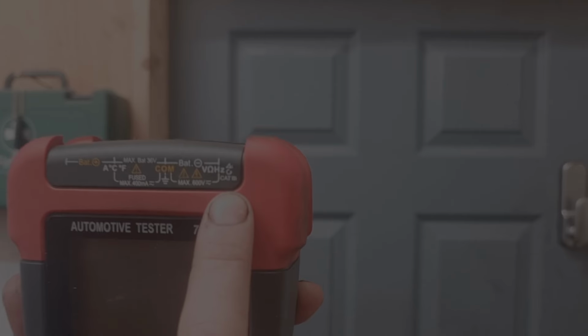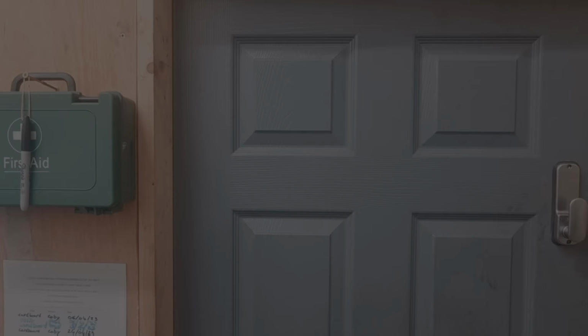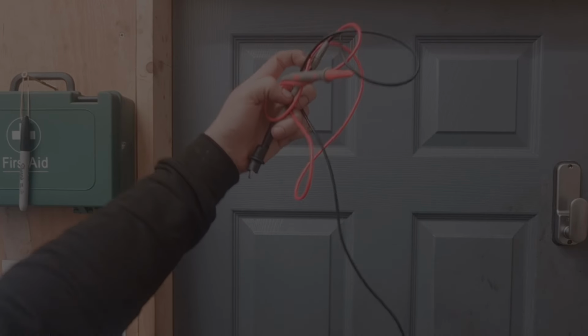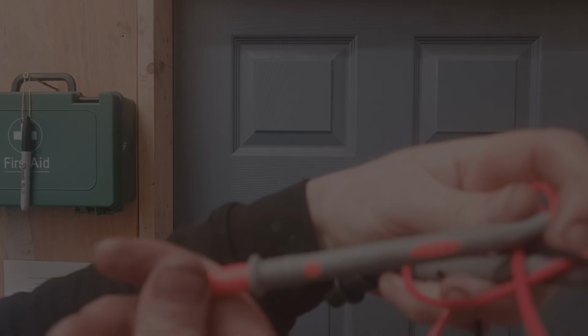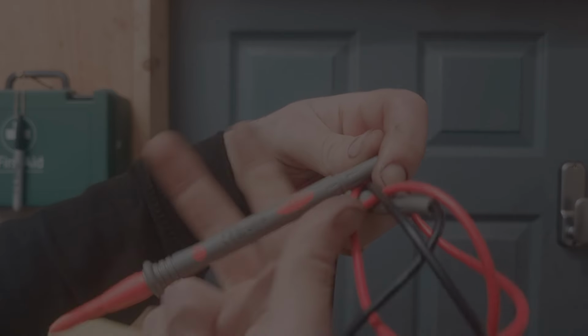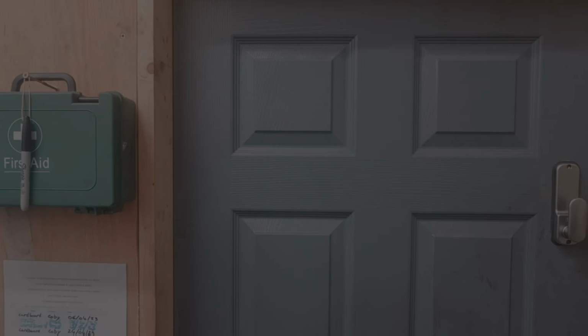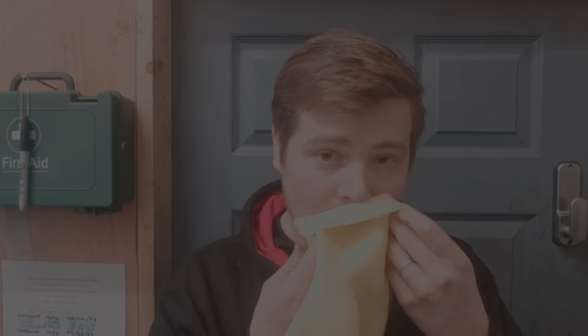Some of the tools we're using include a multimeter, and the multimeters have to be category 3, and so do the leads. You have to be careful with these because a lot of leads aren't actually rated. You'll see they're cat 3 because they have cat, if the camera will focus, they say cat 3 on them. The other thing we're going to be using is gloves and goggles. The gloves have to be the right type, in good condition, and you have to test them.